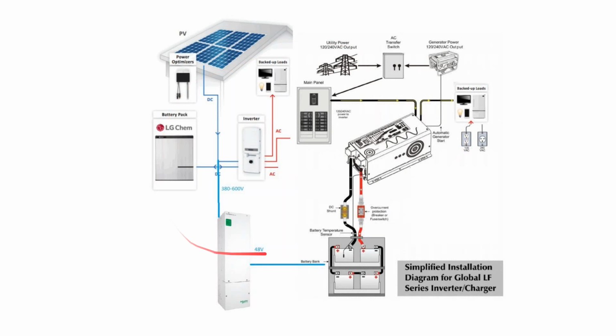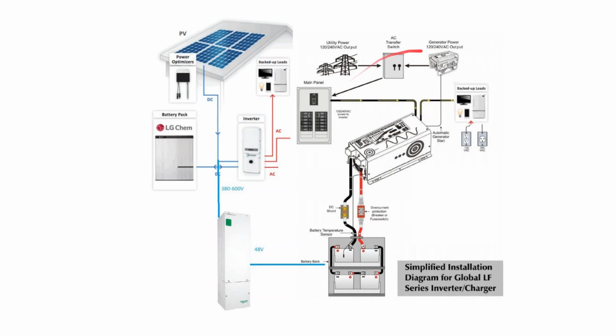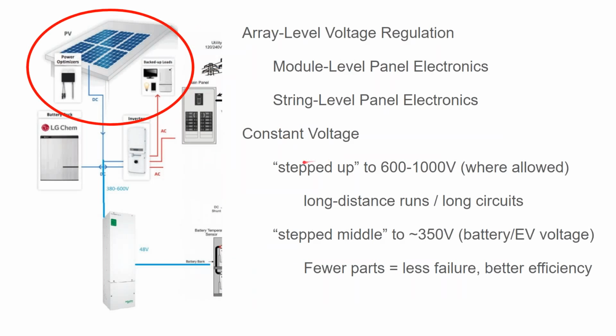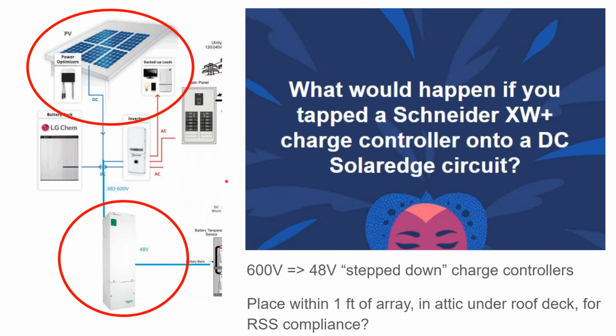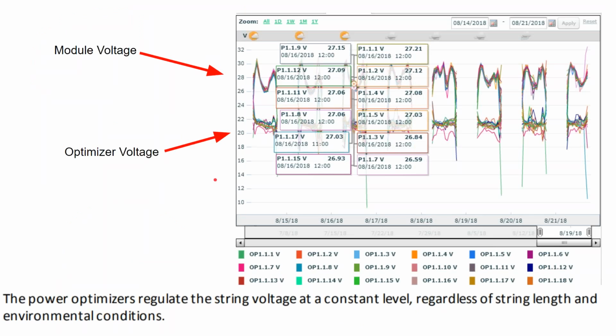So this configuration shows a shared DC bus, high voltage, feeding both a high voltage lithium ion battery bank and a 600 volt charge controller that charges a 48 volt battery bank on a generator interlock switch, which can be switched over during a power outage. This way, your solar array remains grid tied and can backfeed the grid and sell back, but you could also switch around and just as easily use the exact same system in an off-grid setting.